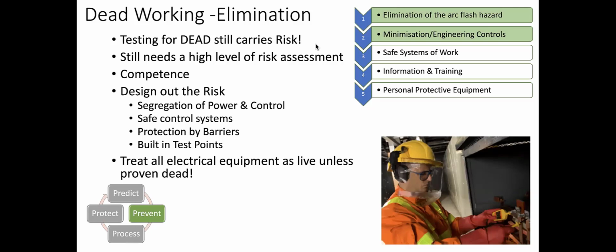Next is equipment design. One of the points I'd made was to try and design out the risks so people aren't testing on live equipment. That means segregation of power and control, safe control systems, protection by barriers and built-in test points. And finally, treat all electrical equipment as live until proven dead.